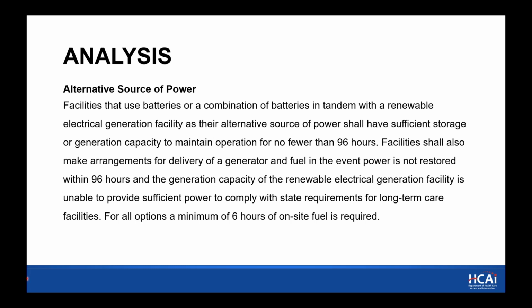Alternate source of power. Again, straight from the bill, facilities that use batteries or a combination of batteries in tandem with a renewable electrical generation facility as their alternate source of power shall have sufficient storage or generation capacity to maintain operation for no fewer than 96 hours. Facilities shall also make arrangements for delivery of a generator and fuel in the event power is not restored within 96 hours, and the generation capacity of the renewable electrical generation facility is unable to provide sufficient power to comply with state requirements for long-term care facilities. For all options, a minimum of 6 hours of on-site fuel is required. So for what we'll call the microgrid solution or on-site renewables, you will need to provide provisions for a temporary generator to be connected without altering the existing wiring at the facility.